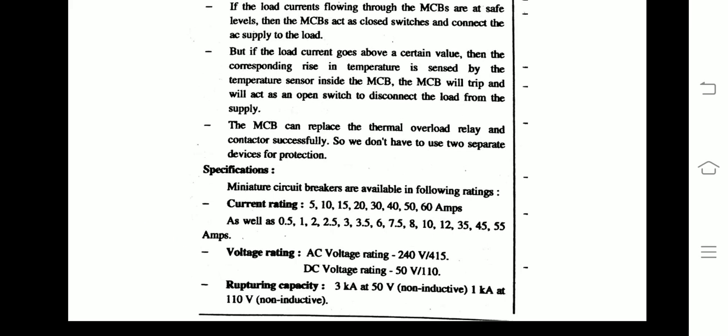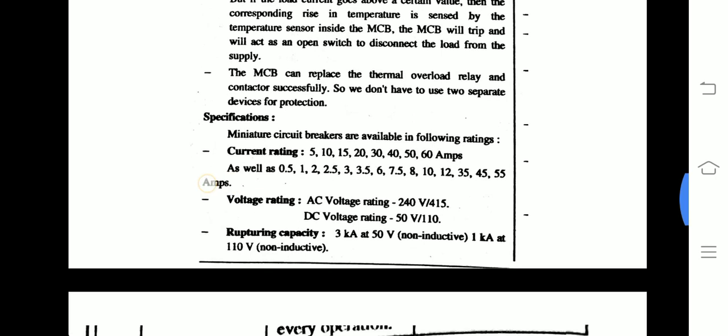The Miniature Circuit Breaker is available in the following current ratings: 5 ampere, 10 ampere, 15 ampere, 20 ampere, 30 ampere, 40 ampere, 50 ampere, and 60 ampere — that is, 5 to 60 ampere. The voltage rating for AC is 240 volt to 415 volt, and for DC it is 50 volt to 110 volt.